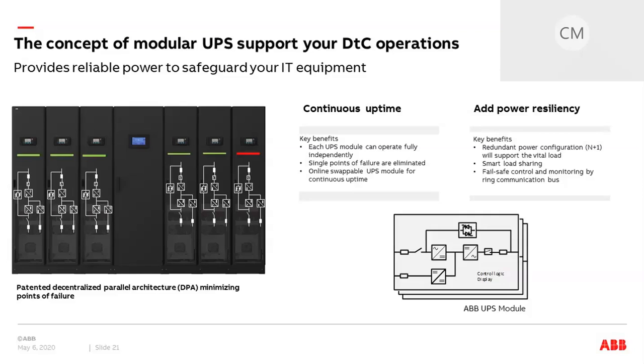As a market leader in the UPS technology, ABB is a pioneer introducing advanced concepts in modern UPS designs. First, ABB Modular UPS has a decentralized parallel architecture named DPA. With this architecture, each UPS module is equipped with its own rectifier, inverter, battery charger, static bypass, and control logic for autonomous operation. This patented architecture maximizes power availability due to the redundancy for critical components, avoiding single point of failure inside the system. This is the reason why we can bring continuous uptime and resiliency with the DPA technology.